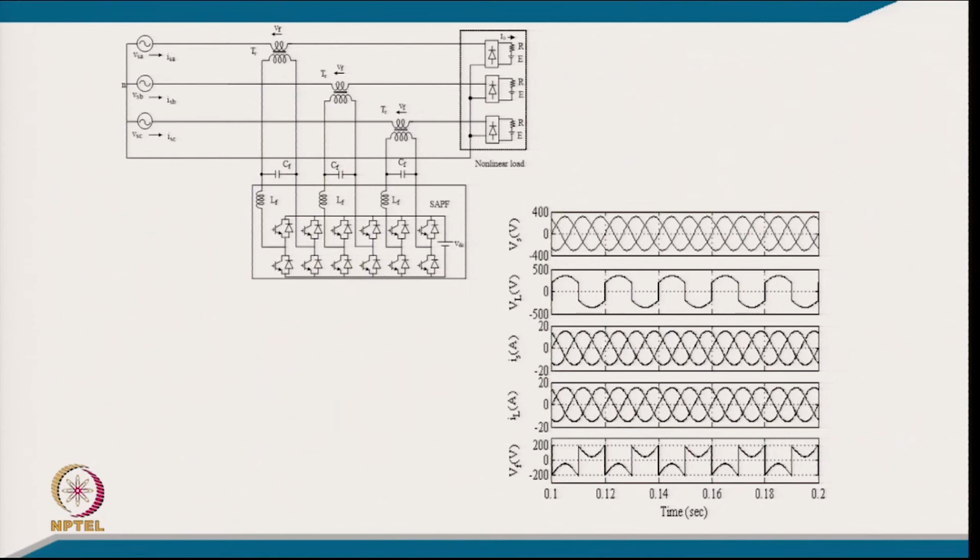So, this is the system. We have a 3-phase 4-wire system. So, we have a load, a diode rectifier with typically an RE load. We are charging the battery and all 3 are symmetrical in nature. So, such a load will certainly cause excessive neutral current if series active filters are not connected. So, we are connecting series active filters, and by making a complete model, the very purpose is that we must have a sinusoidal, balanced current in phase with the phase voltage, and the neutral currents will be eliminated automatically.